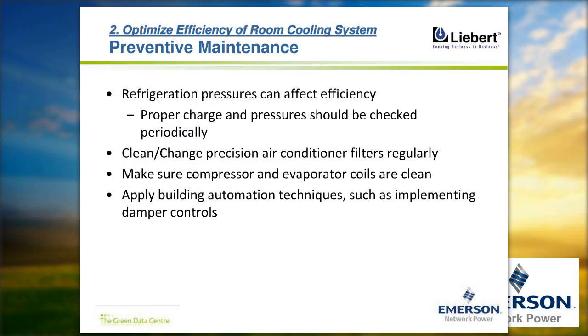Air conditioning devices need the most maintenance. They have a lot of wear and tear and a lot of challenges. So it is expected that you do regular preventive maintenance with respect to maintaining the pressure of refrigerant and cleaning the filters and coils, which will also help improve energy consumption by way of higher efficiency from the cooling system. Every 3 months you should check the filters and the pressure gauges and check whether the refrigerant is properly maintained. It is also recommended that we clean all the compressor and evaporator coils, at the condenser side as well as the compressor side.